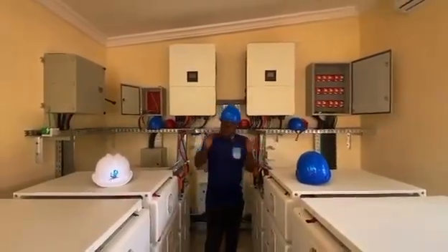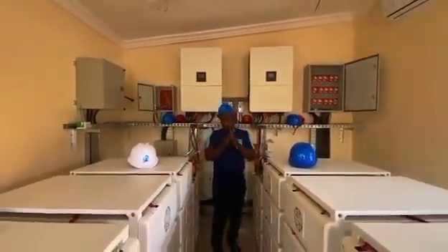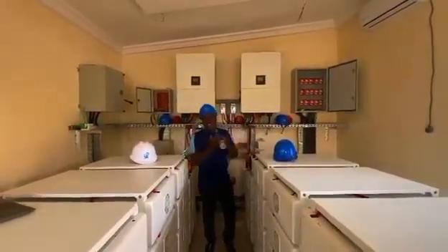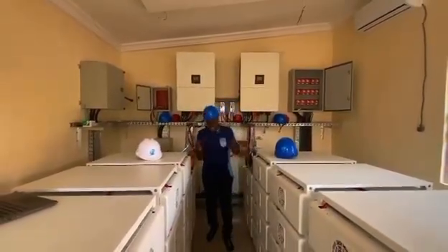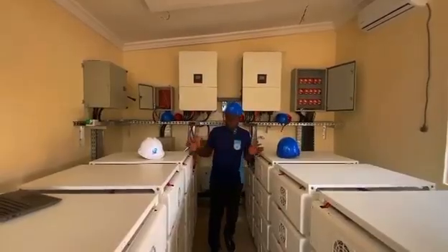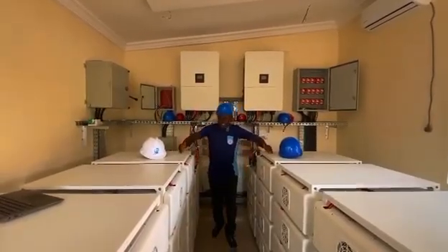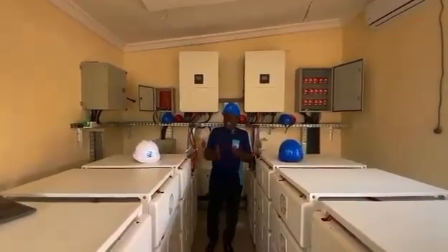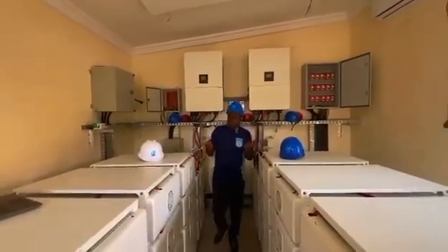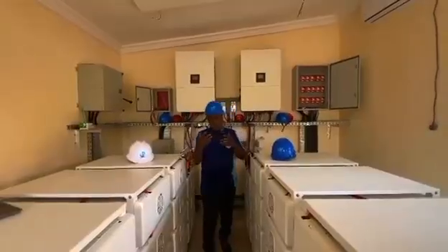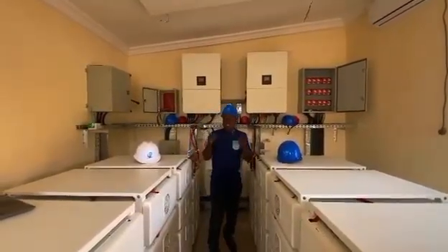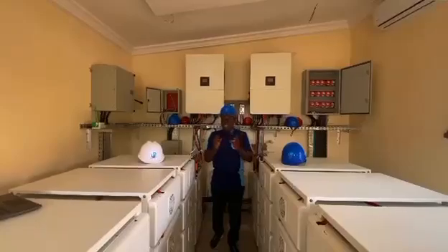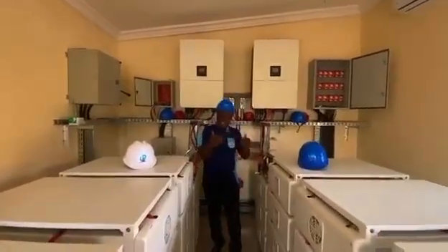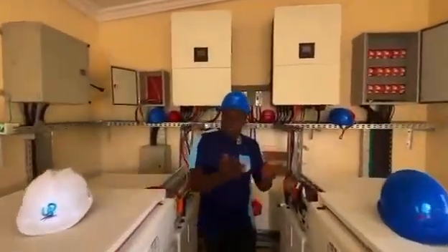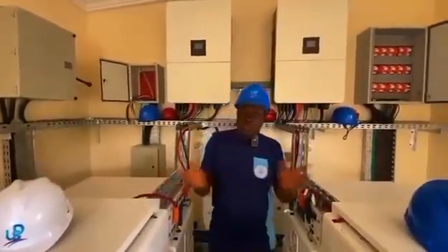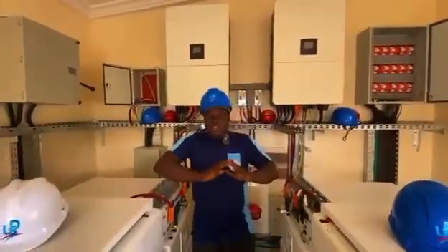The consumption during the daytime at peak is 40 kilowatts, and at night we are giving them 20 kilowatts consumption. So if you calculate, this battery is enough to take this campus for 24 hours, except on days of low autonomy. Those are the only exceptions where they might need to bring in either their generator for 1 hour, or NEPA lights for maybe 1 hour, to assist in fully charging this battery.